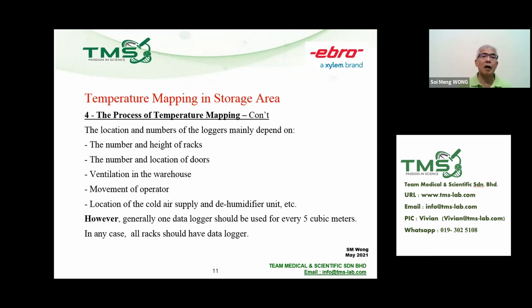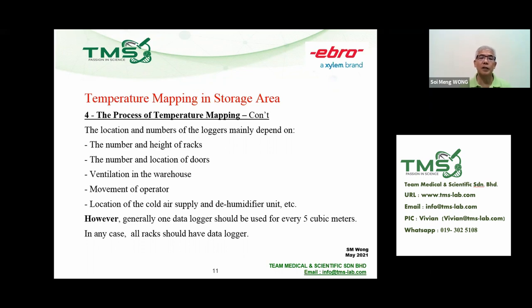A common question is: how many loggers should I use and where should I place them? The location and number of loggers mainly depend on the number of racks and their height or width, the number and location of doors, ventilation in the warehouse, movement of operators or forklifts, and the location of cold air supply and dehumidifiers. As a general rule, one data logger should be used for every five cubic meters, and in any case all racks should have a data logger.